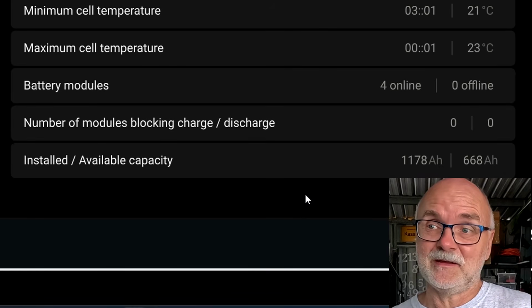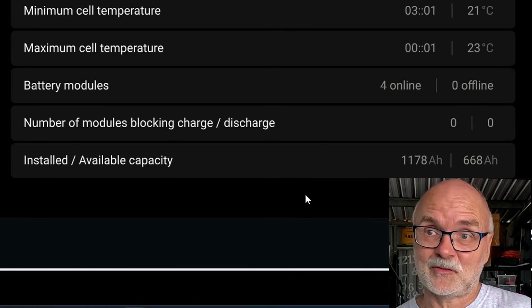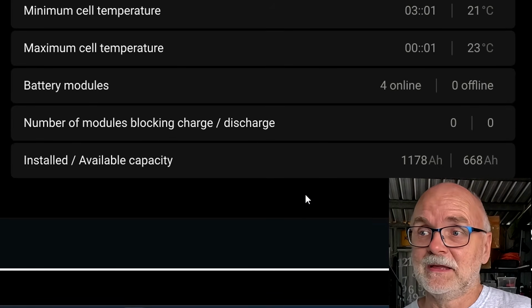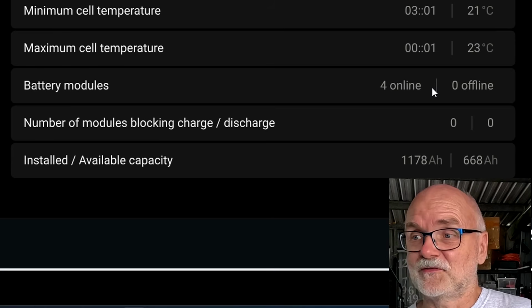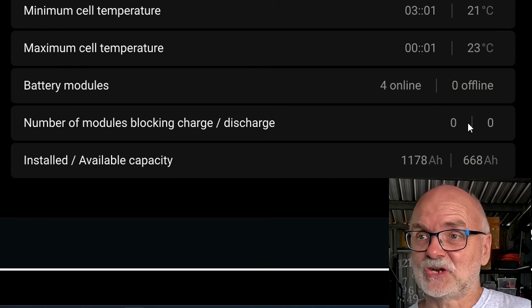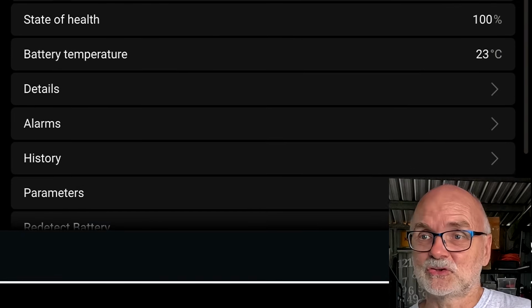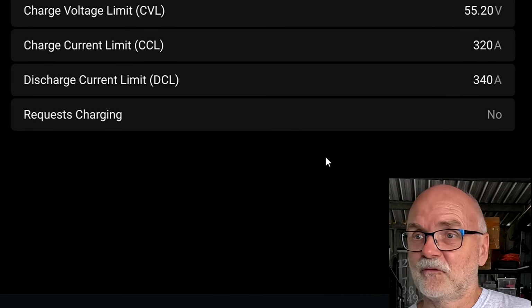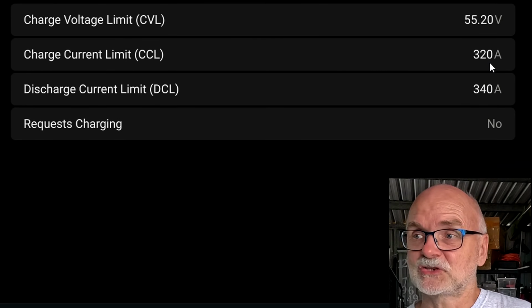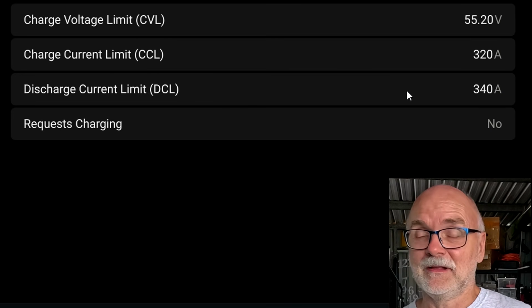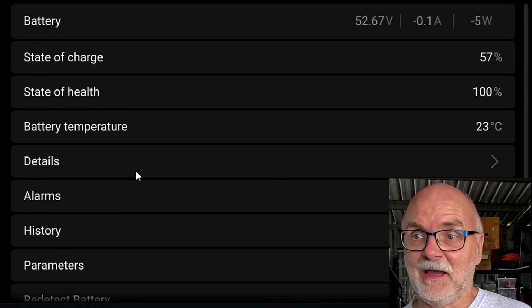I've now changed the maximum charge current in this BMS back to 100 amps, from 15 to 100. And you can see here all 4 modules are online. Nothing is blocking charging or discharging. And we should also see here the full requested charge current of 320 amps and 340 discharge. So everything is back to normal as it was before. 4 batteries are online.